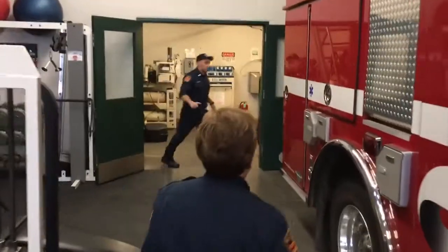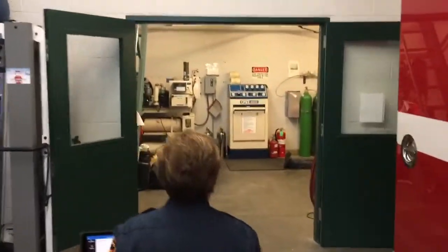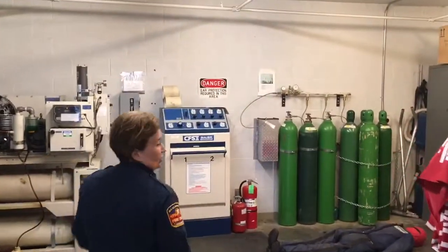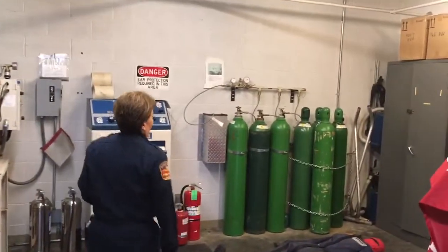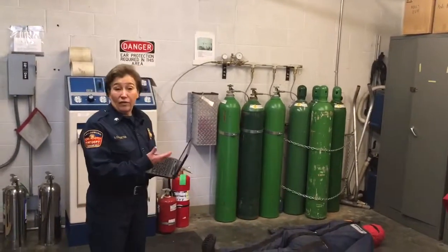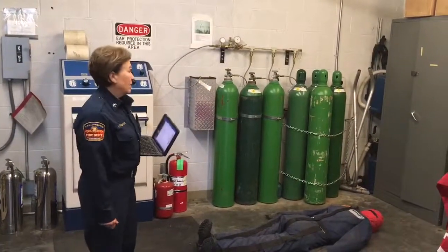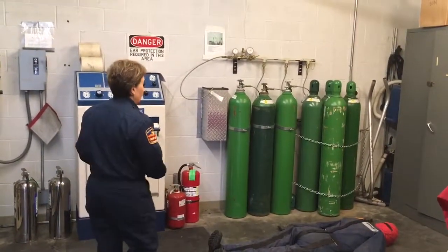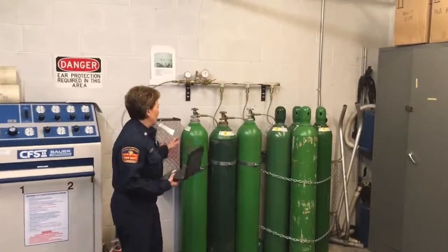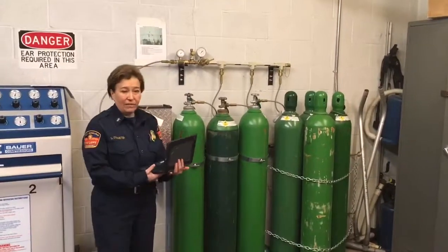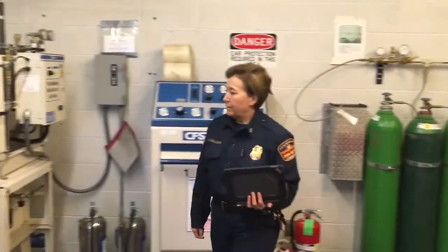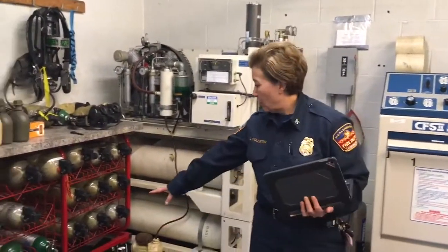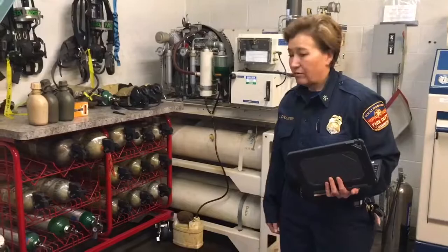So one of the things that we have is medical gases. Oh, and then we also have our dummy here, but as you can see, our tanks are secure. We're not exempt because we have over 1,000 cubic feet of medical gases, and so we fall into a range, and we're not exempt for hazardous materials reporting. So we have all our oxygen here. We have a guy on the floor. These don't count; they're compressed air cylinders, but some small oxygen over there secured.